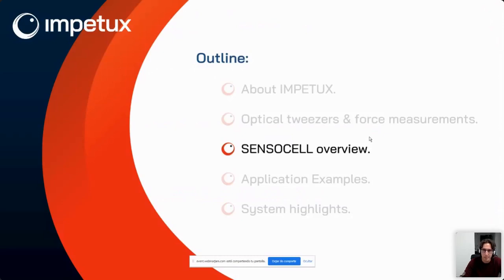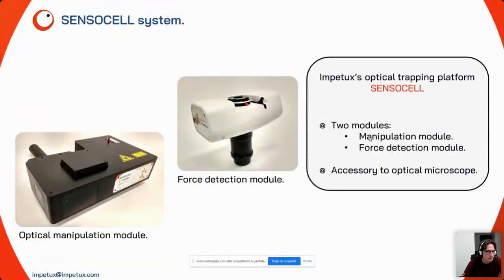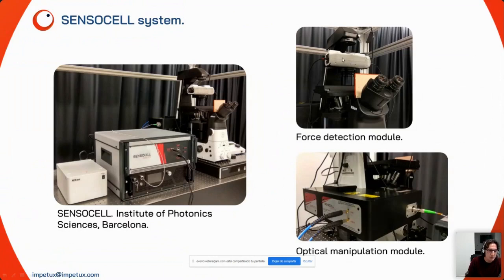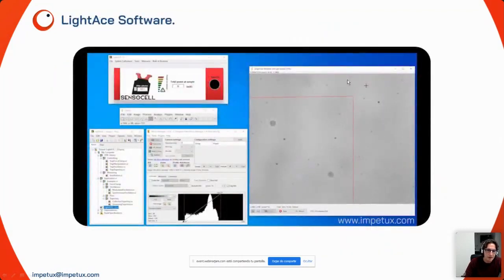The system is called SENSOCELL, consisting of two modules: the optical manipulation module, which generates the optical traps, and the force detection module. Both are accessories to an optical microscope. The complete system includes the force sensor, the optical module, electronics, and the laser. The optical module attaches to the back port of the microscope via a laser fiber. The force detection module substitutes the condenser lens but maintains the imaging capabilities of the microscope by letting light pass through.